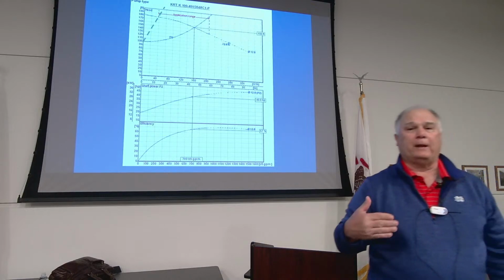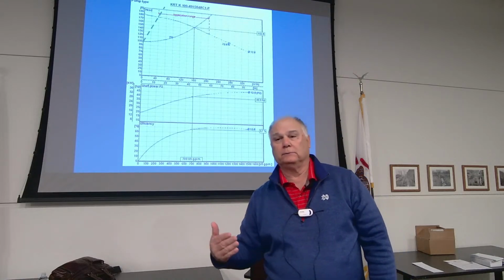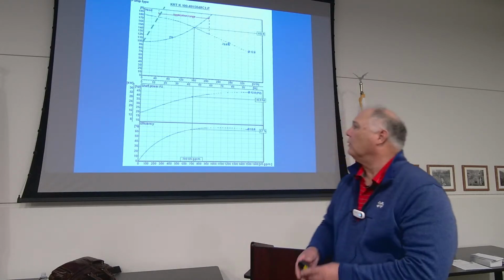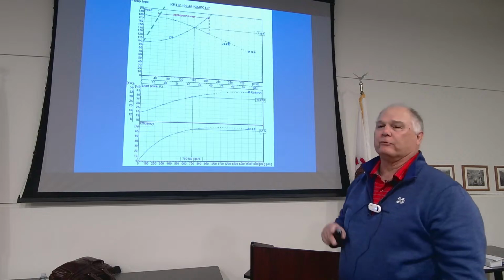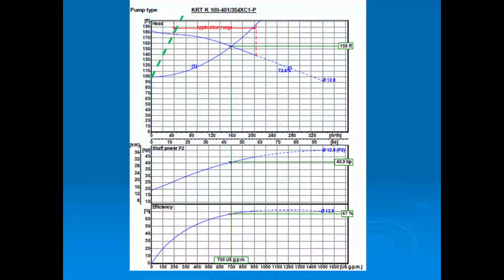So all your motor controls are going to start tripping out at 20 amps or 15 amps or lower or higher, because over time, that amperage is going to heat up the motor. You want to protect that motor. Let's design something properly. So that's what all these different lines on the curve mean. What's that curve to the left where it says application curve, the green one? It's a cavitation curve. You don't ever want to operate to the left of the curve because the water can't get out of the pump. Then you will cavitate that impeller.